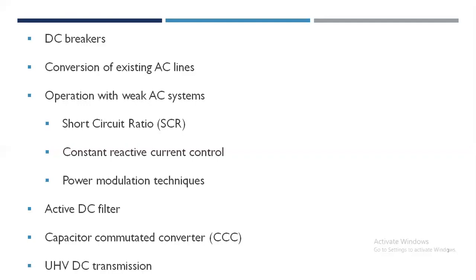The last one, UHV DC transmission system. Ultra high voltage UHV DC transmission at plus minus 800 kV is being considered for transmission of large blocks of power above 3000 megawatt for distances beyond 1500 km in China, India, South Africa, and Brazil, where large hydropower resources available in remote areas are developed. A bipolar HVDC line operating at plus minus 800 kV can transmit power in the range of up to 5000 or 6000 megawatt with two 12 pulse converters per pole. It is claimed that information currently available on the flashover and withstand characteristics of air gaps is adequate for the design of plus minus 800 kV systems.